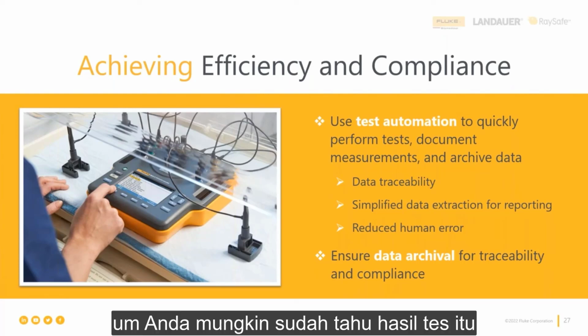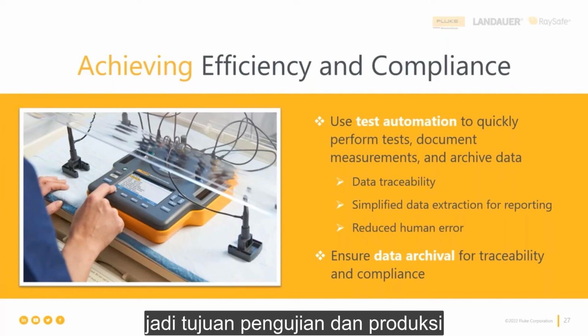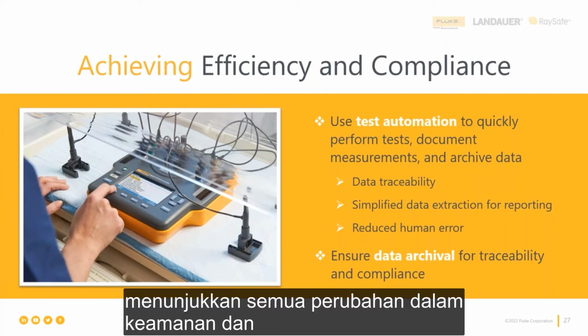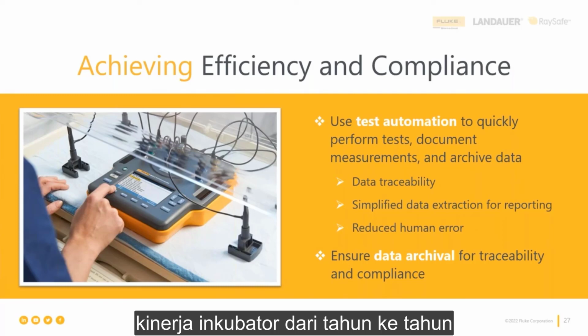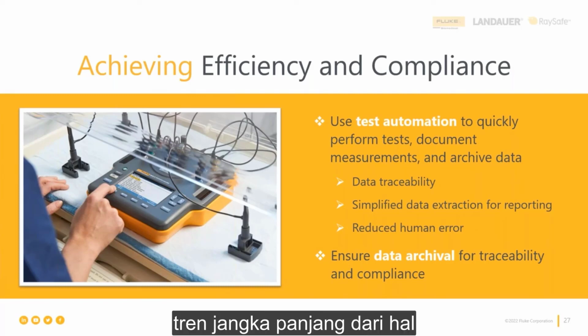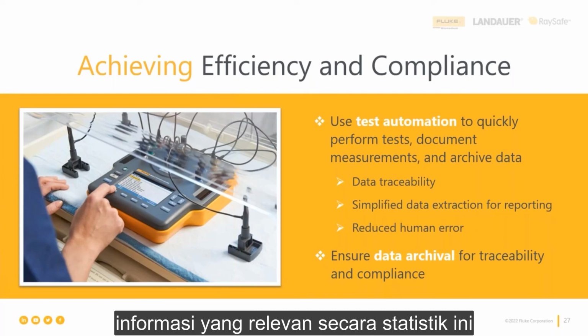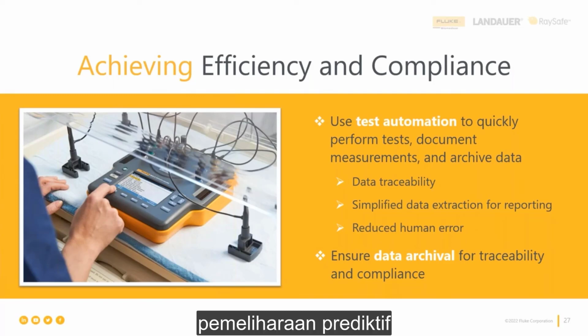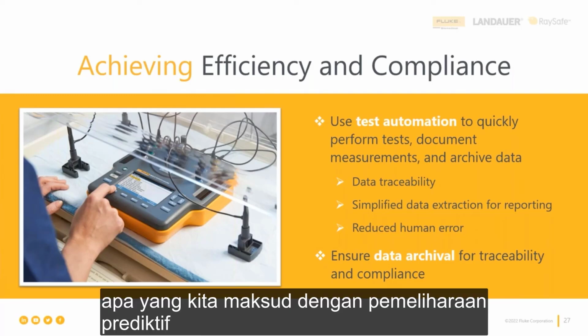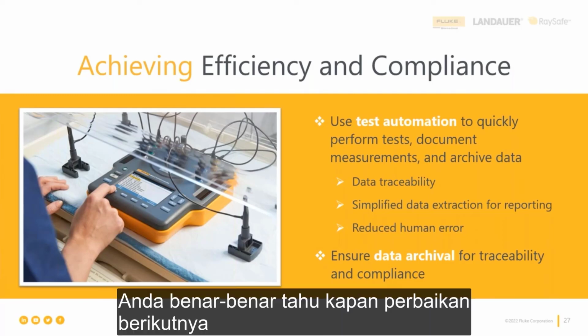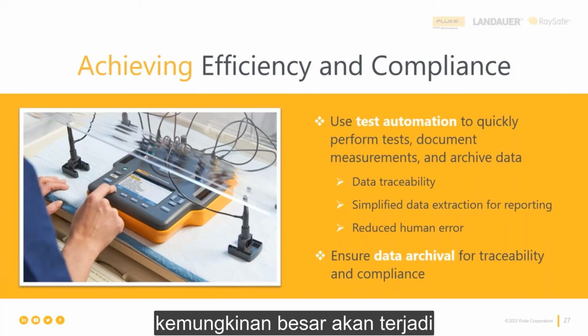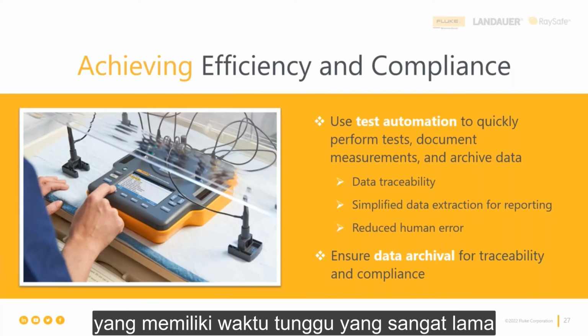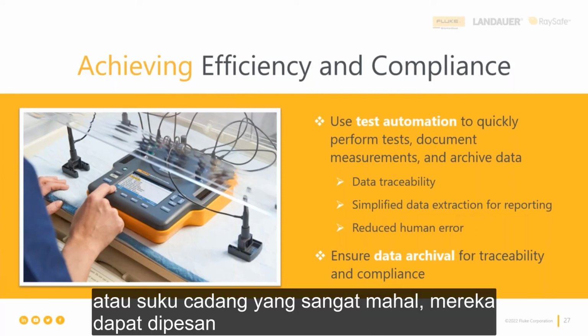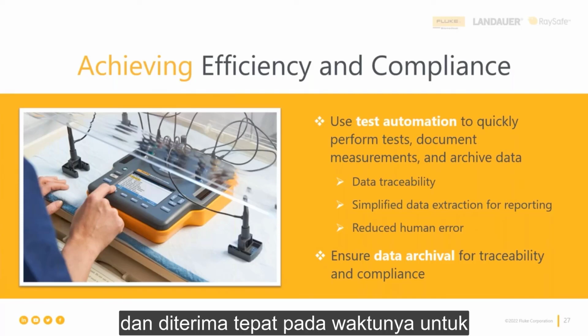You probably already know that test results should always be archived, right? The purpose of testing and producing those test results is to have a continuous stream of data showing all changes in the safety and performance of the incubator year over year. Long-term trending of this statistically relevant information provides the basis for predictive maintenance. What we mean by predictive maintenance is that you know when the next repair is most likely to happen, so that parts, especially those with very long lead times or very costly parts, can be ordered and received just in time for the upcoming repair event.